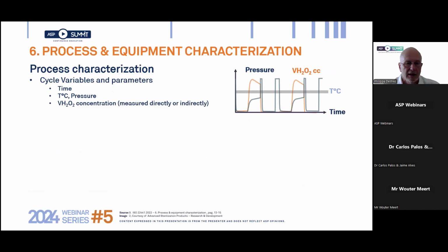So paragraph 6 is still in the domain of the sterilizer manufacturer, but it goes into more details, and you'll start seeing on these slides concepts which are closer to what you know from sterilizer equipment. One added value of ISO 22441 compared to ISO 14937 is that it lists the variables. You remember the definition that I gave earlier, which might be measured to adequately control an H2O2 sterilization process. So time, temperature, pressure, and H2O2 concentrations are the minimum variables that must be controlled by a sterilization process. So manufacturers can add additional variables, such as control of the plasma, but at a minimum, time, temperature, pressure, and H2O2 concentrations are the most important. Time is obvious, I think.